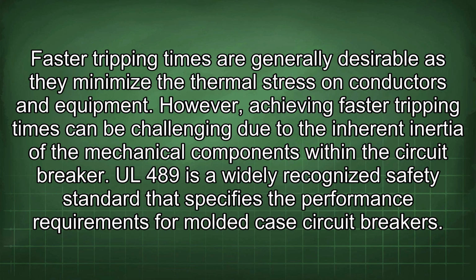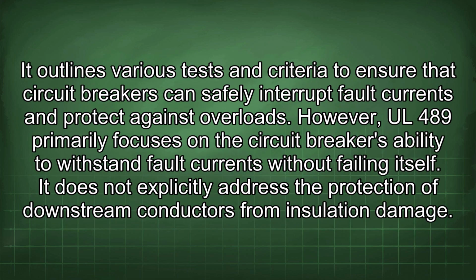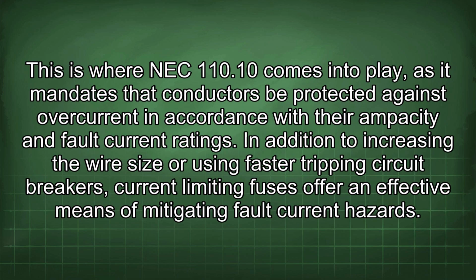However, achieving faster tripping times can be challenging due to the inherent inertia of the mechanical components within the circuit breaker. UL 489 is a widely recognized safety standard that specifies the performance requirements for molded case circuit breakers. It outlines various tests and criteria to ensure that circuit breakers can safely interrupt fault currents and protect against overloads. However, UL 489 primarily focuses on the circuit breaker's ability to withstand fault currents without failing itself. It does not explicitly address the protection of downstream conductors from insulation damage. This is where NEC 110.10 comes into play, as it mandates that conductors be protected against overcurrent in accordance with their ampacity and fault current ratings.